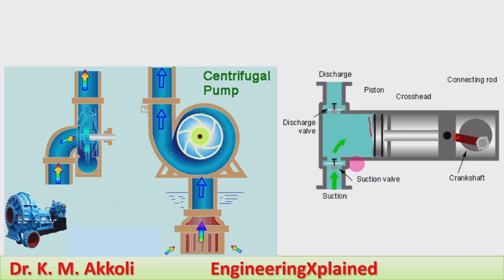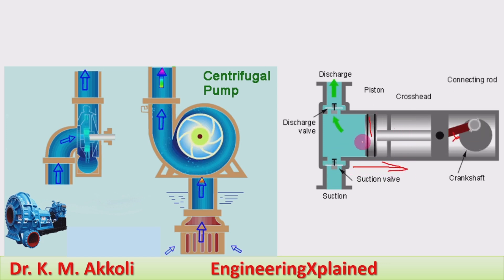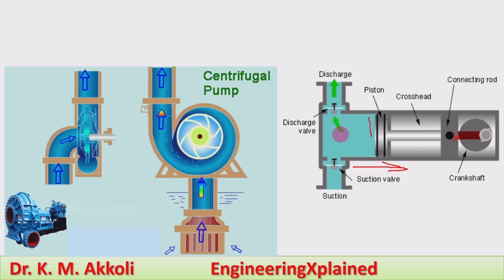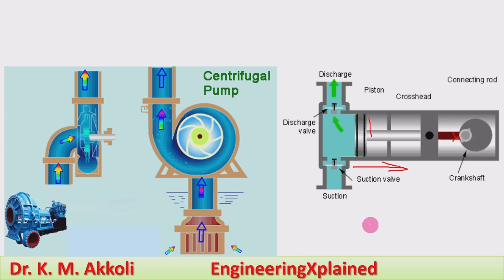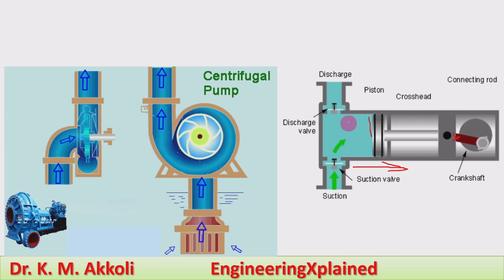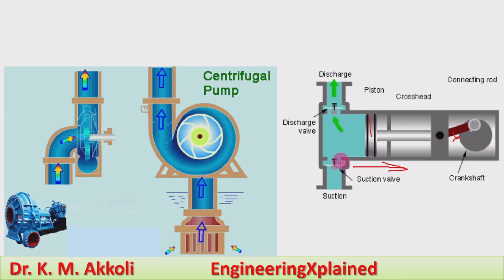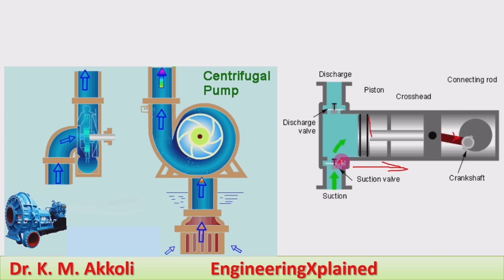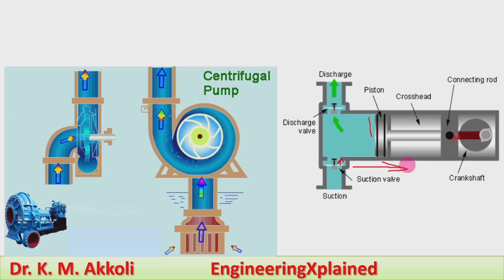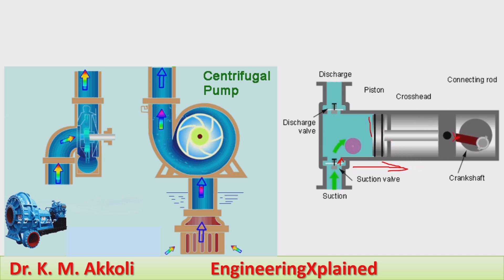This is the piston. The piston reciprocates inside the cylinder. When the piston is moving backward, a vacuum is created inside — the pressure falls below atmospheric pressure. Since outside pressure is atmospheric and inside is below atmospheric, there is a vacuum. Then the delivery valve gets closed, and due to that vacuum, the inlet valve gets opened and fluid flows into the cylinder during the return stroke of the piston.